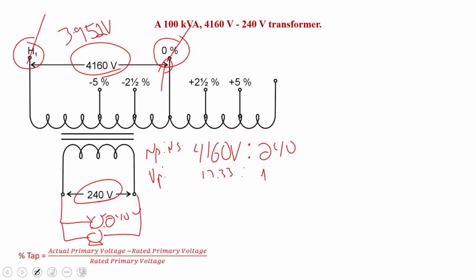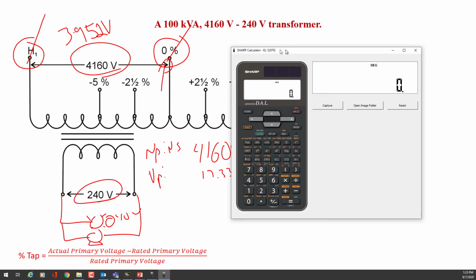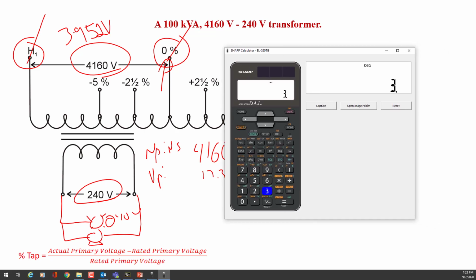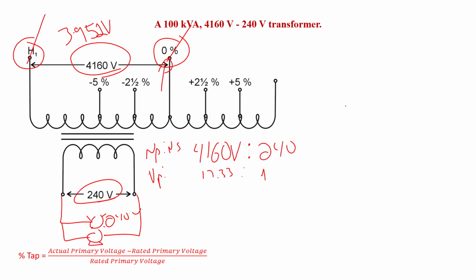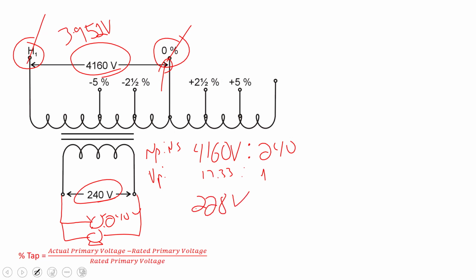So if I only put 3,952 volts on this transformer, I will take 3,952 and divide it by 17.3333. I'm only going to get 228 volts out on the secondary, so 228 volts. Now that's not really going to be very good for my loads. If I'm only getting 228 volts, these loads are not going to work accordingly.